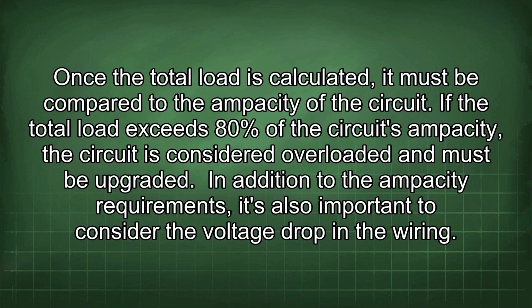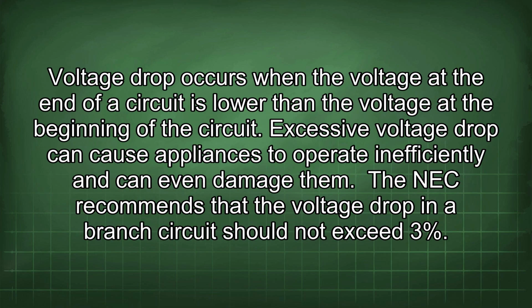In addition to the ampacity requirements, it's also important to consider the voltage drop in the wiring. Voltage drop occurs when the voltage at the end of a circuit is lower than the voltage at the beginning of the circuit. Excessive voltage drop can cause appliances to operate inefficiently and can even damage them. The NEC recommends that the voltage drop in a branch circuit should not exceed 3%.